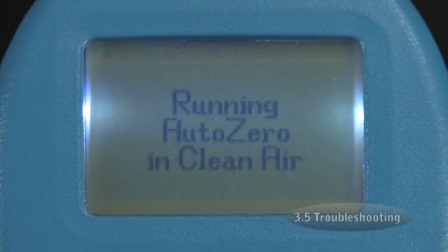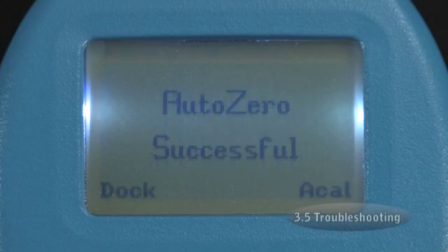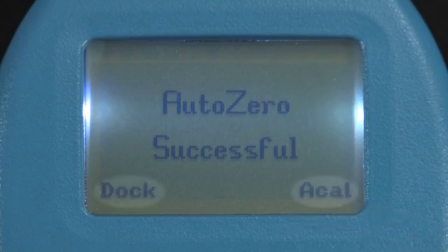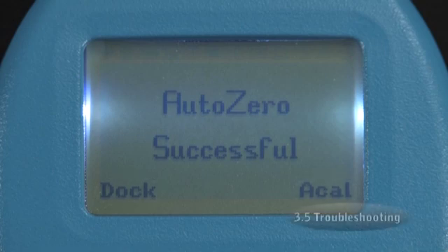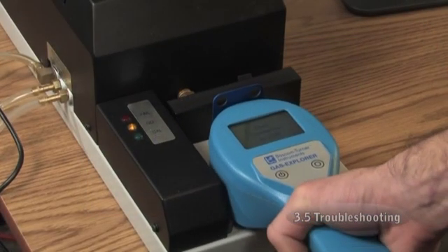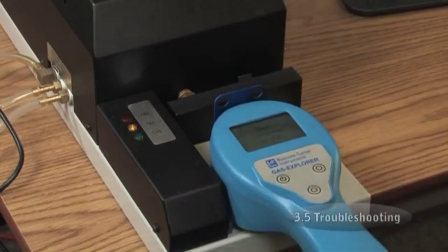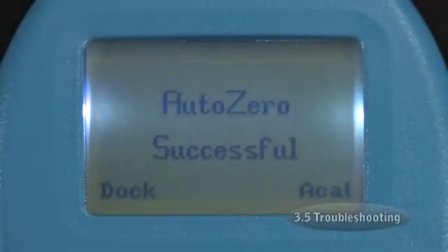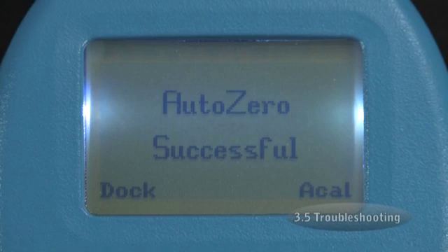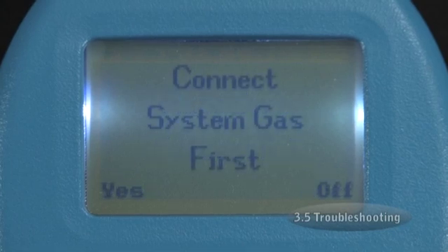The display will show Running Auto Zero in Clean Air for several seconds. When Auto Zero Successful appears on the display, you will be given the choice to either dock or ACAL the Explorer. For those with docking stations, press the left button and proceed as you typically would when calibrating on the dock. 2 docking cycles are required for a new filament routine. After the first docking cycle completes, the Explorer will prompt you to turn it back on and run another docking cycle. For those wishing to ACAL, press the right button and you will be prompted to connect system gas first.